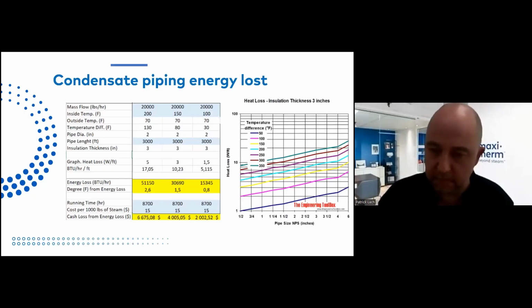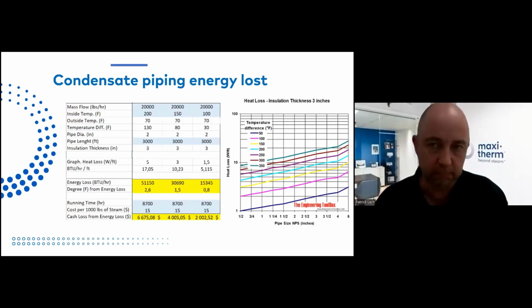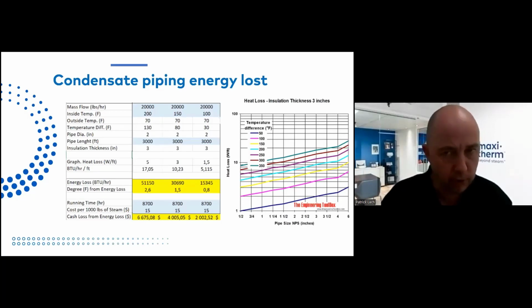One pound of steam travels between 6,000 and 10,000 feet per minute. One pound of water with 1 BTU per Fahrenheit travels 600 feet per minute. So the friction is much higher on hot water than steam. Steam is so fast, right?